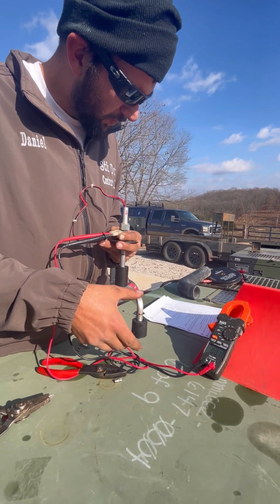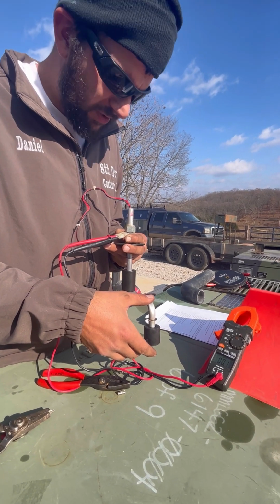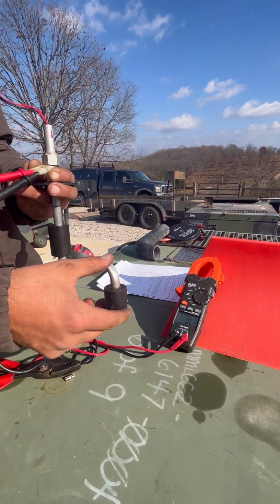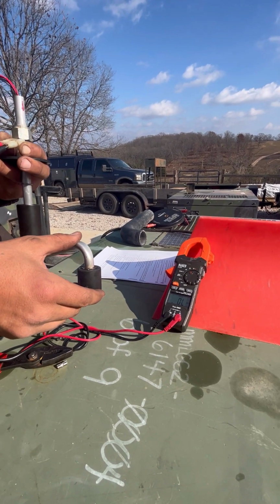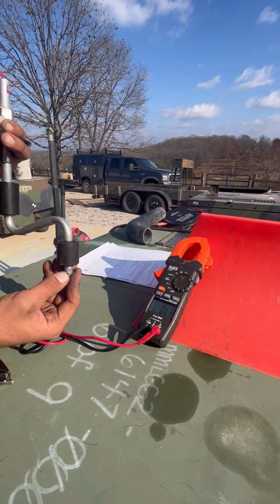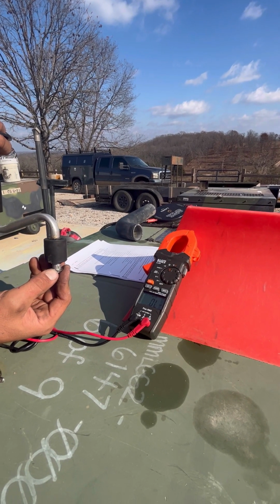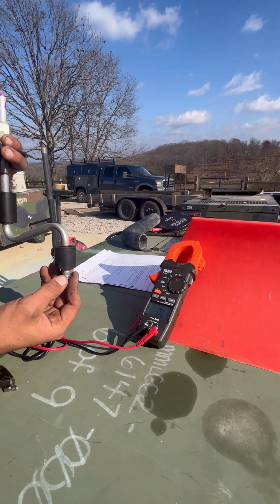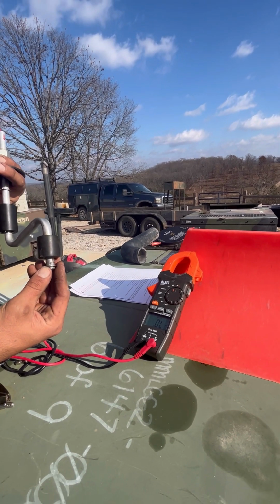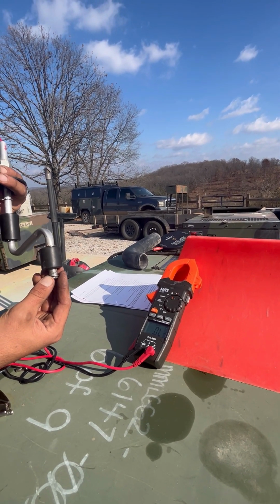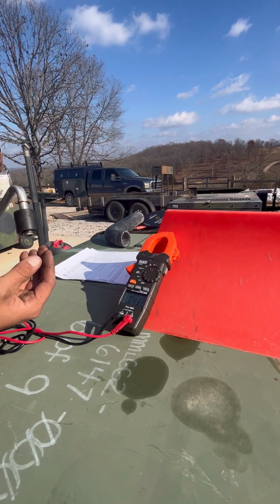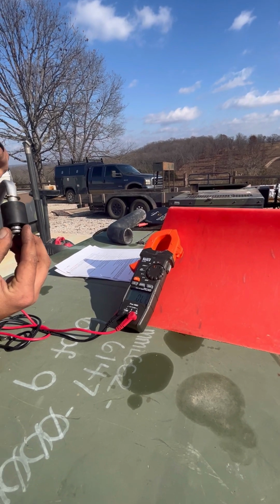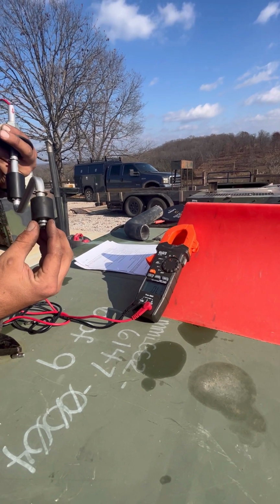So with the float to the full position, the multimeter should read an open circuit, which it does. The multimeter should read continuity a quarter inch before the float reaches the bottom position. So we're open right now. There's continuity all the way to the bottom. And there's about a quarter inch.